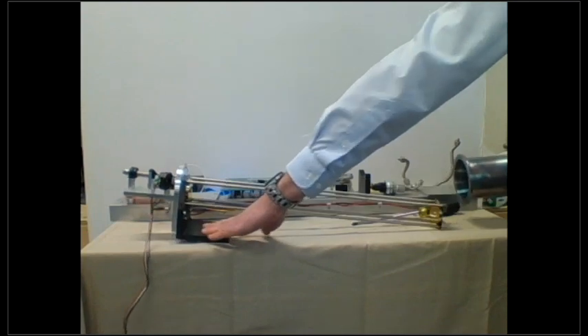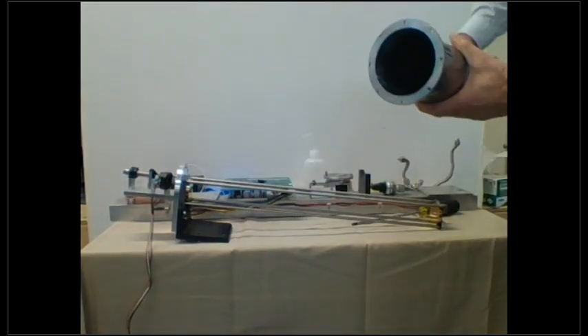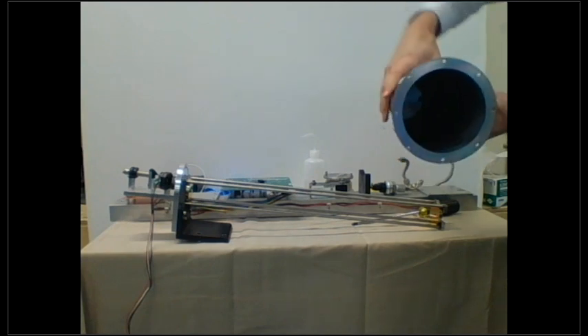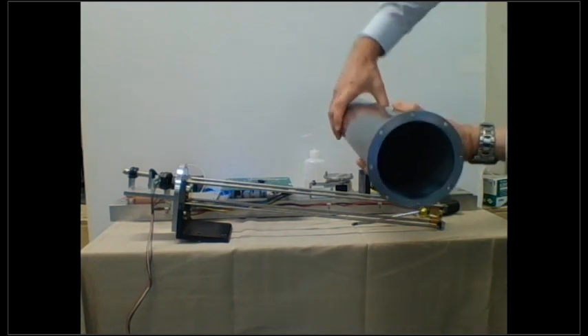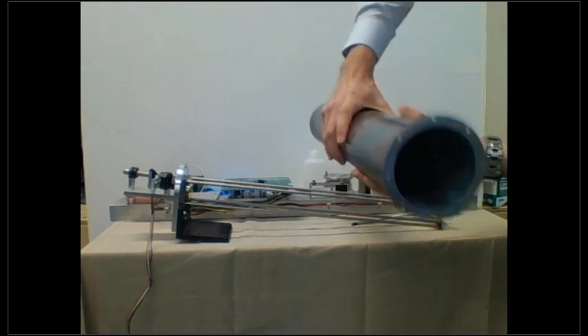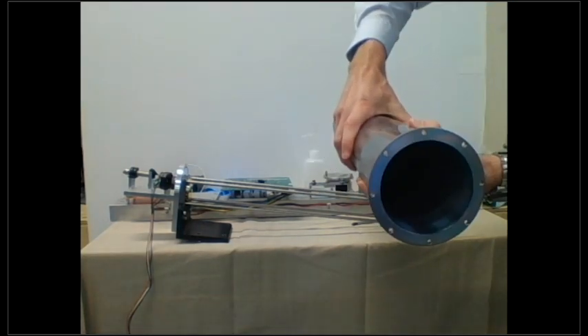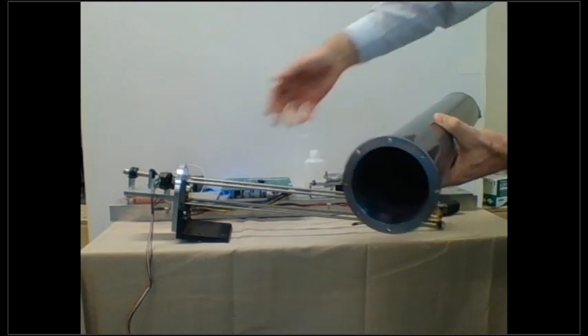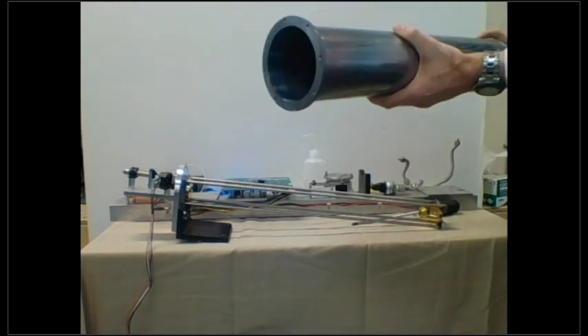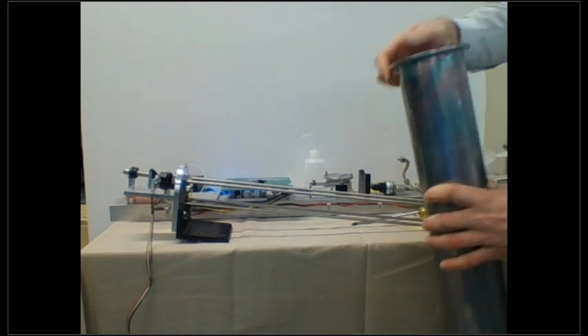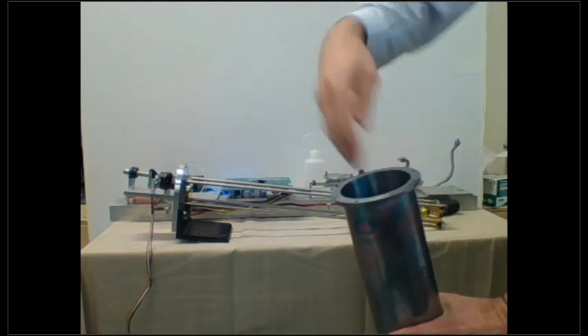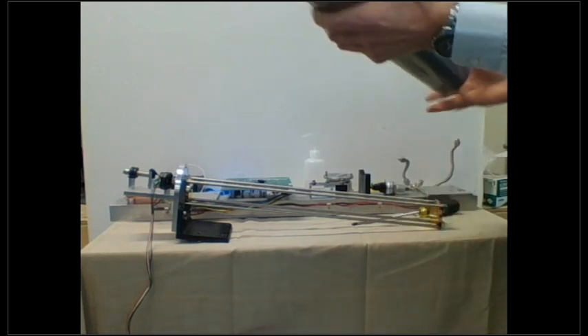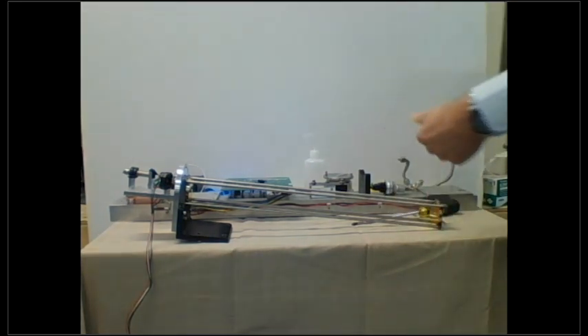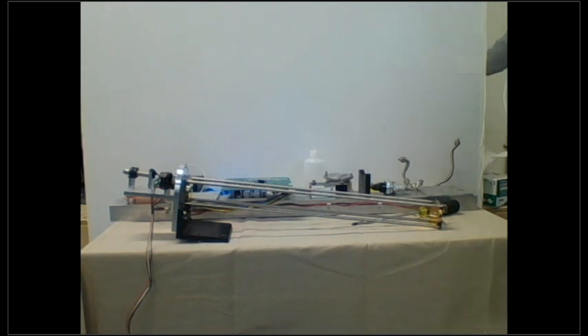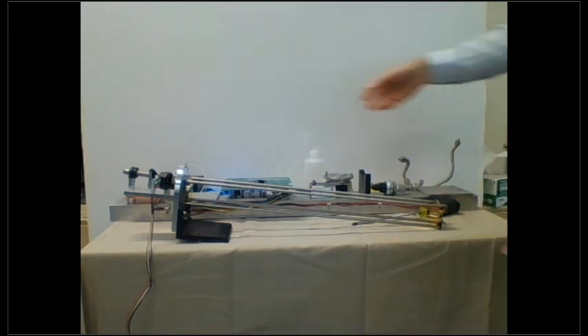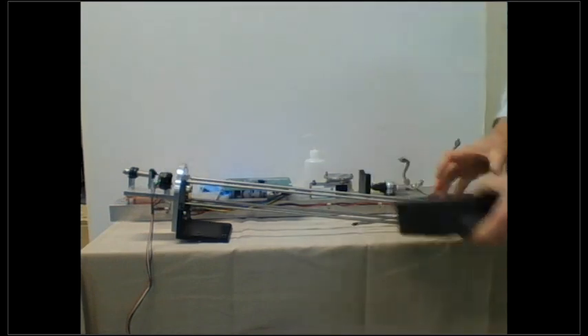Be a little bit careful with it. There's a tube that actually extends down into the cell to make sure that we have adequate gas mixing. I don't know if you can see that extended tube inside there, but it may want to rub up against the cell. If this gets dirty, you can just use a paper towel or something to wipe the sides of it down. I'm going to set that aside for the time being. So this, again, gives you access to the cell itself. So you can see this is the optics cage here. There's your far mirror and your near mirror.